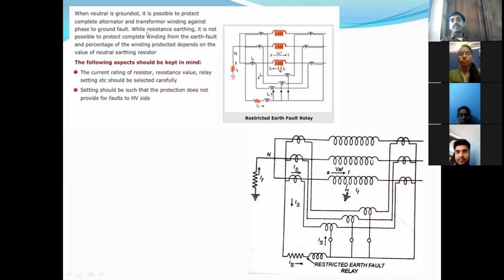But when resistance earthing is used, it is not possible to protect the complete winding from earth fault, and the percentage of the winding protected depends upon the value of the earthing resistor. Depending on the earthing resistor value, a certain amount of the winding is protected and the rest is unprotected. The unprotected portion ranges from 15 to 20%. It all depends upon the resistance value here.